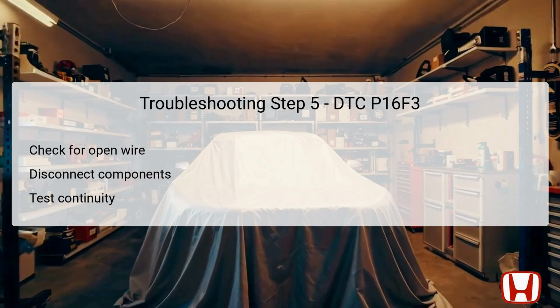If continuity is confirmed, this indicates the wire is intact, leading the technician to move forward in the process. Conversely, if continuity fails, it confirms an open circuit requiring repairs, which will typically include inspecting wire insulation, repairing connections, and possibly replacing components to ensure the relay operates properly.